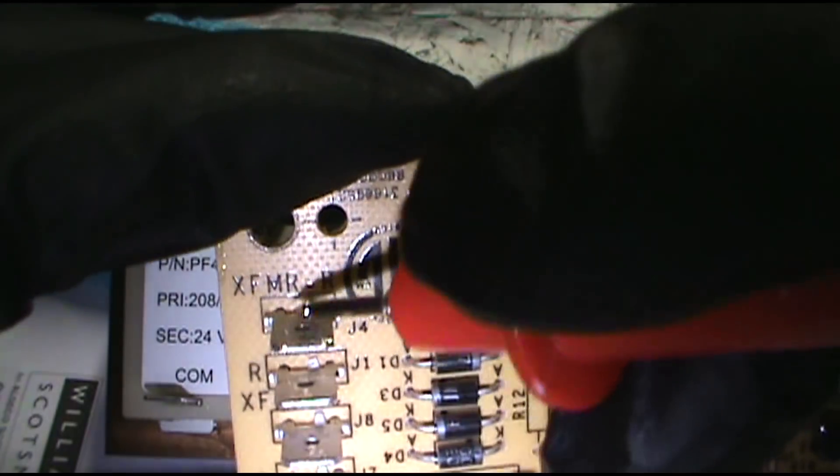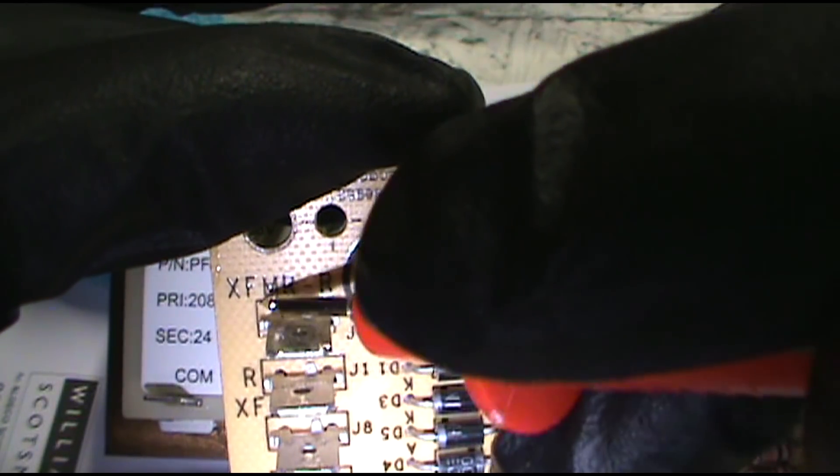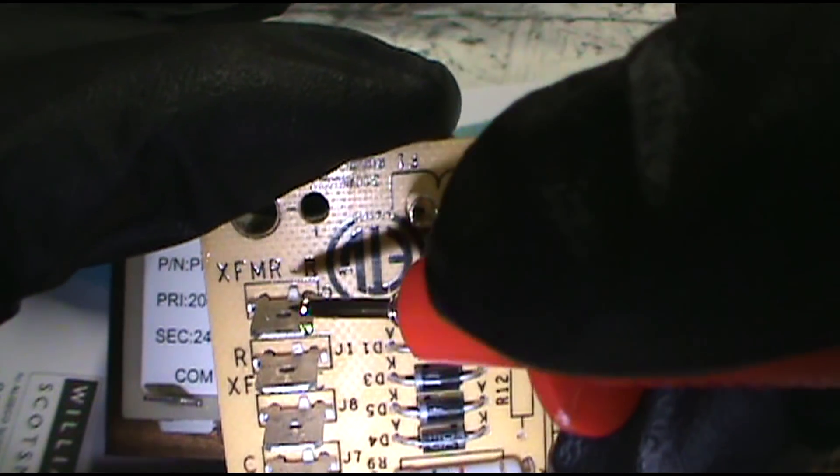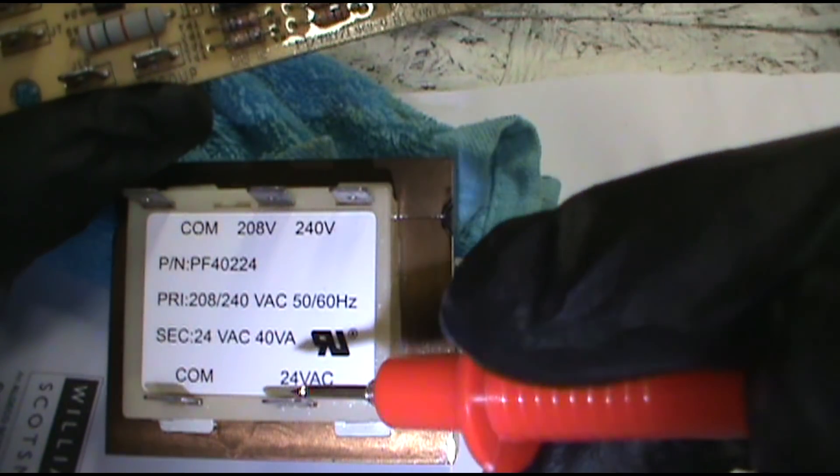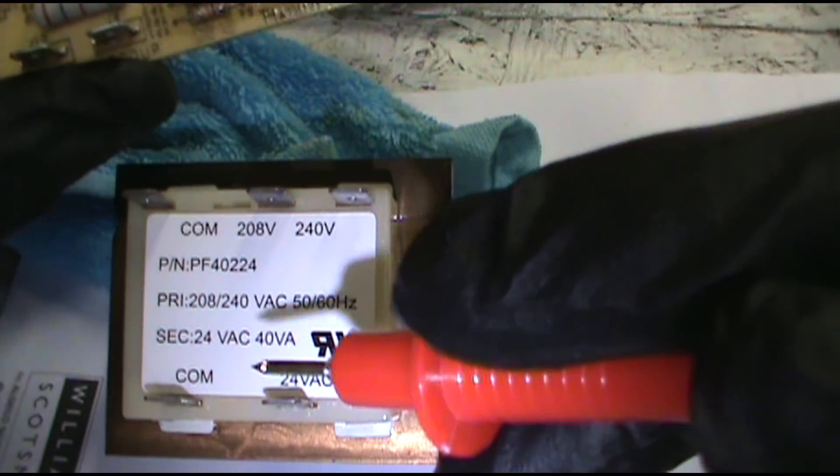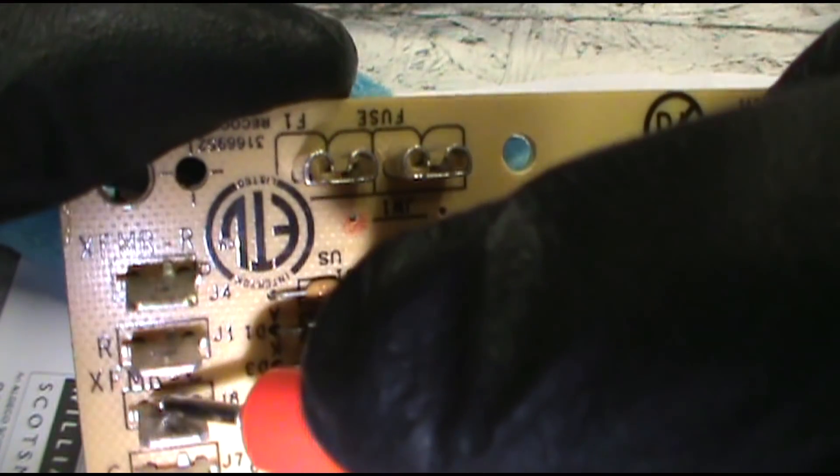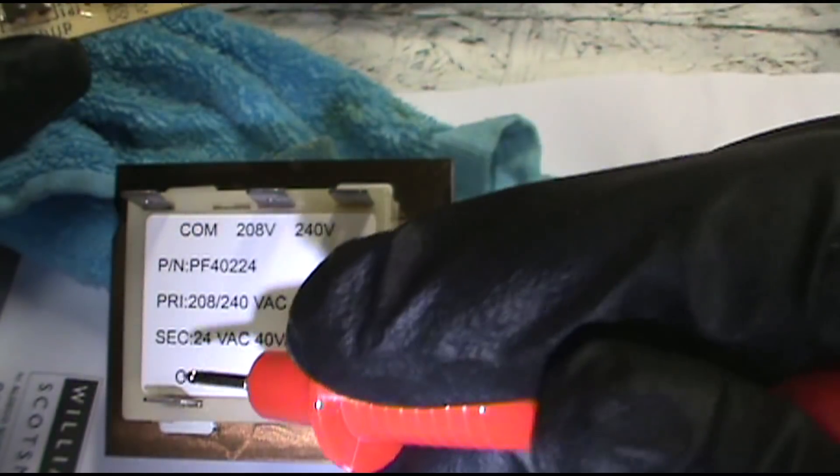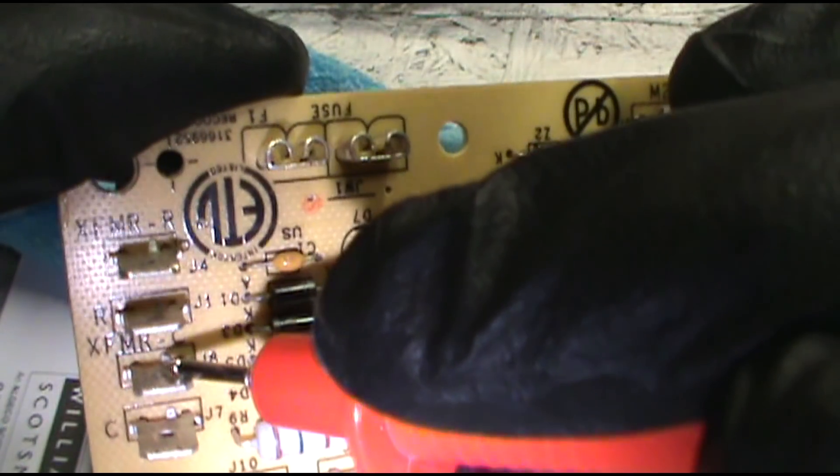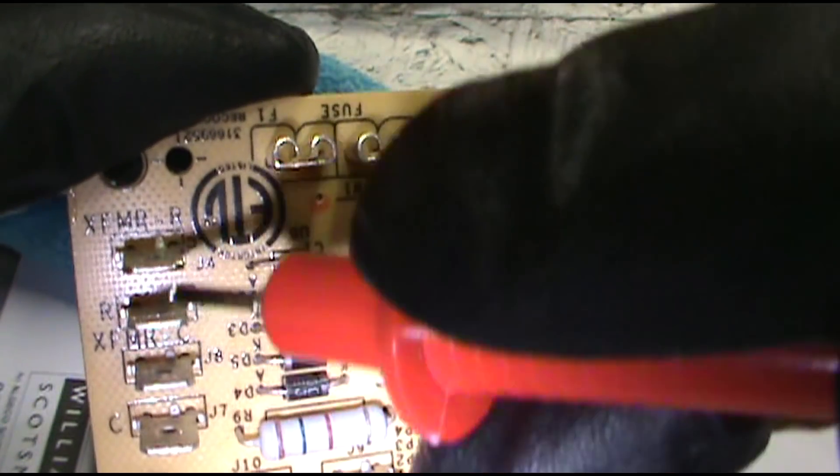So the XFMR stands for transformer, and this will be the 24 volts coming into the board from the transformer. So it comes out here, comes out of this terminal and into here. And the XFMR C, C stands for common. This comes out of the common on the transformer, comes out and into here. So these two are the power coming in, the 24 volts coming into the board.